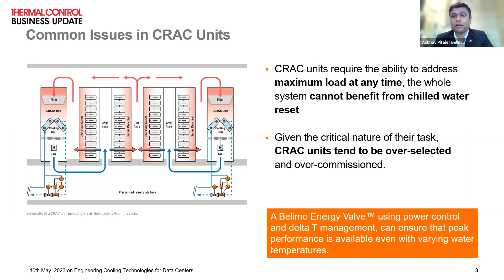Today, as technology has evolved, we've moved from pressure dependent to pressure independent valves, to electric pressure independent valves, with added intelligence to understand the system and monitor delta T - the low delta T syndrome - because CRAC or AHU units' coil efficiency degrades over time. A coil that could handle 50 TR may not handle it after 2 years. It's important to understand if a coil is deteriorating and whether we're moving toward a saturation point.